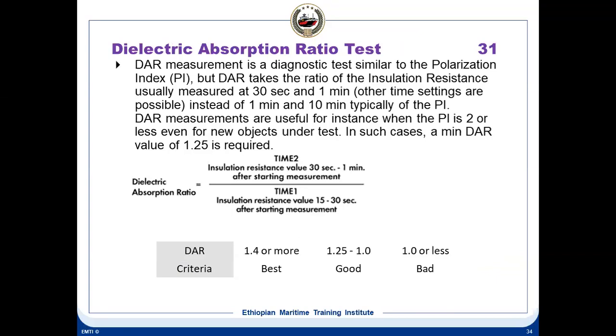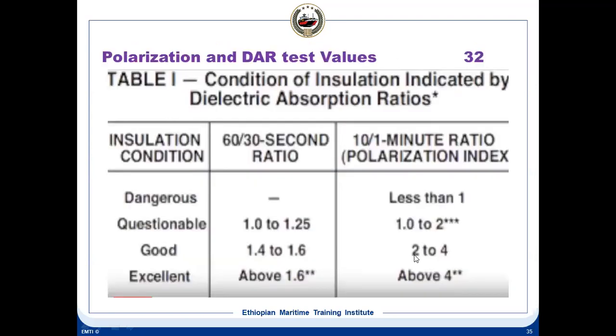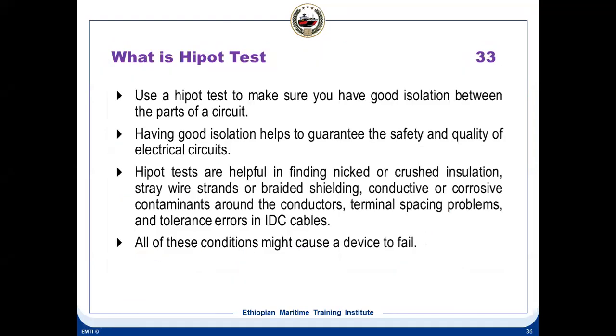What is DAR test? Dielectric absorption ratio test. This is also another type of test similar to the polarization index test, which is carried out, but it is 30 seconds to 1 minute. And here also you can see, DAR of 1.4 or more, 1.2 to 1.0 is considered to be good. If it is less than 1, then it becomes bad. This is also another type of diagnostic test, same as the polarization index test. So for polarization index test, values you can see here: less than 1 is dangerous, 1.0 to 2 is questionable, 2 to 4 is good, above 4 is excellent.